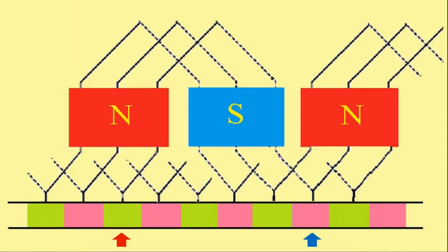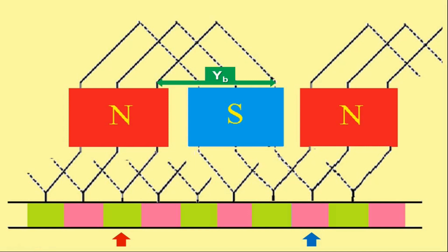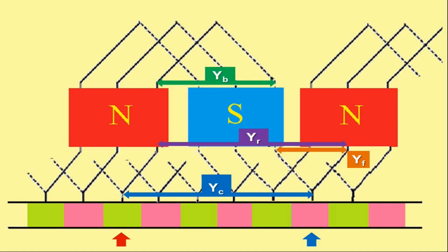In a similar fashion, we may now define the back pitch, front pitch, and resultant pitch of wave winding. The back pitch is the distance between the two sides of a coil connected at the back of the armature. The front pitch is the distance between the second conductor of one coil and the first conductor of the next coil connected to the common commutator segment. The resultant pitch is the distance between the beginning of one coil and the beginning of the next connected coil. And finally, the commutator pitch is the distance between the commutator segments to which the two ends of a coil are connected.